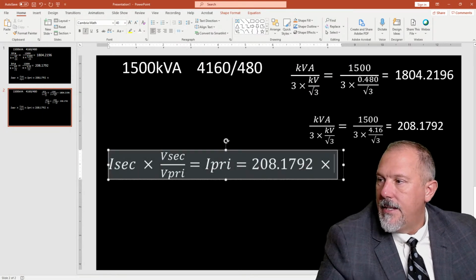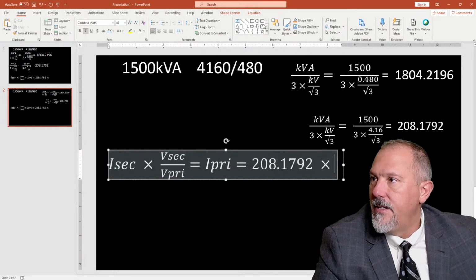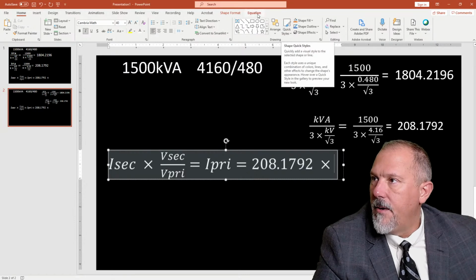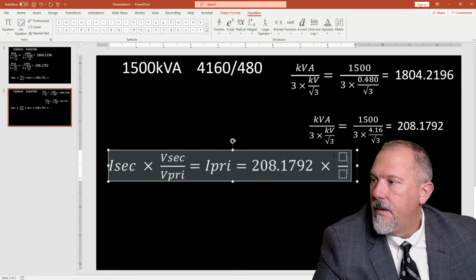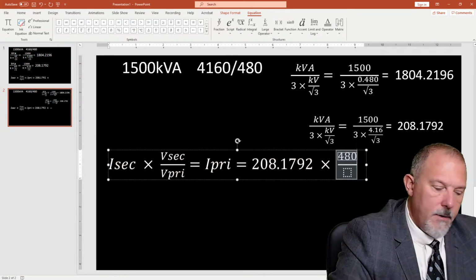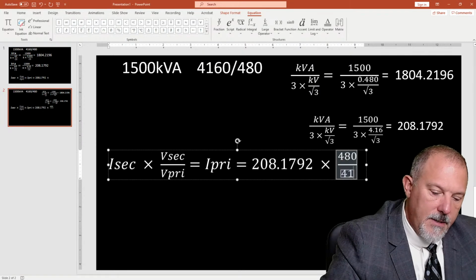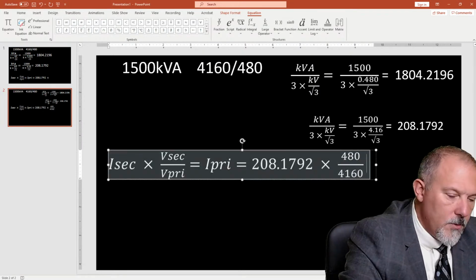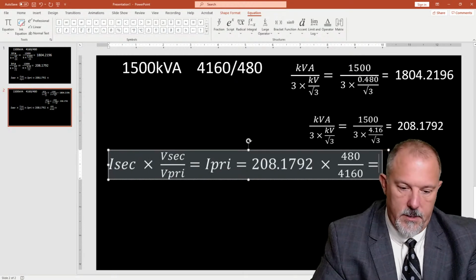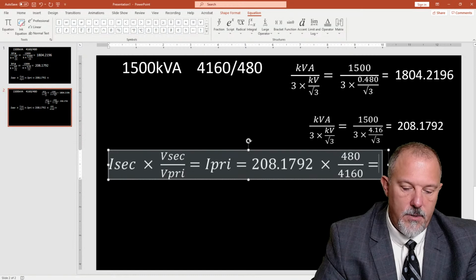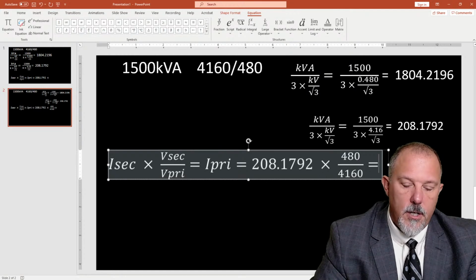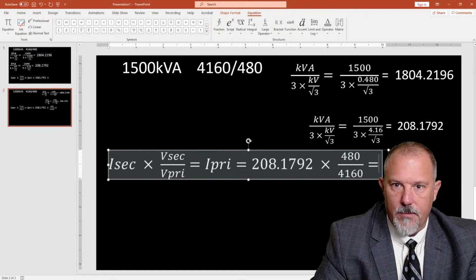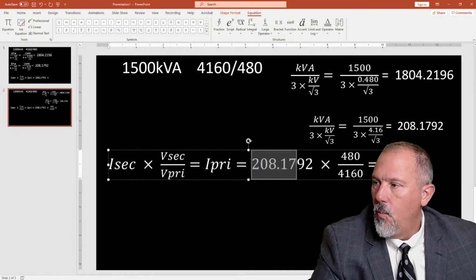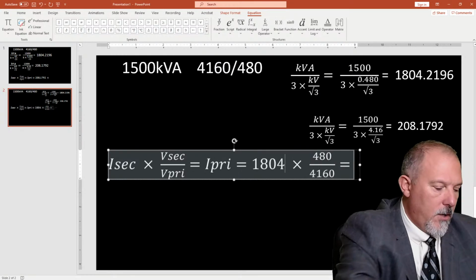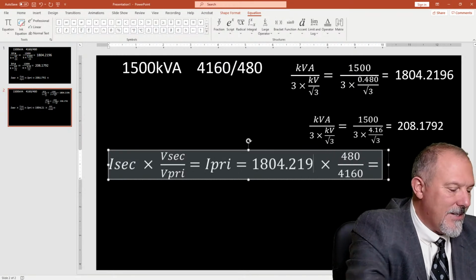So 208 times V primary divided by V secondary, or V secondary divided by V primary. And I'm going to do this: 480 divided by 4160 equals, drum roll please, 208.1792 times 480 divided by 4160. Did I get the right numbers? Nope, I used the wrong number. Whoa, it's I secondary, 1804.2196. Just seen that.